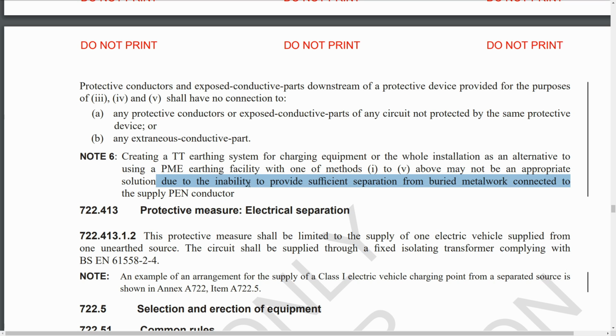This video is not particularly on TT installations, but a key point about installing earth electrodes is that when you install them, they need to be as far away as possible from anything else in the ground, which they could be connected to an alternative earthing system.